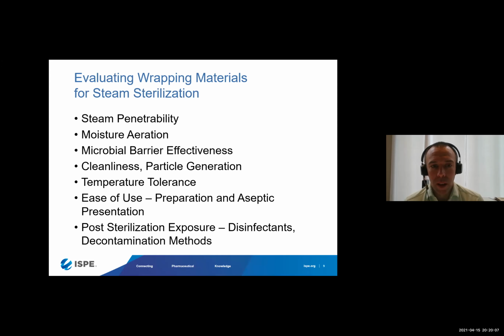to do with how they interact in the sterilization process through the autoclave sterilization. So does the material have good steam penetrability? Can sterilization take place through these wrapping materials? Likewise, are the materials breathable? Do they allow for moisture aeration during the drying in the autoclave? As you probably know, it's important once the materials are sterilized that they also must be dry to prevent recontamination after removal from the autoclave.